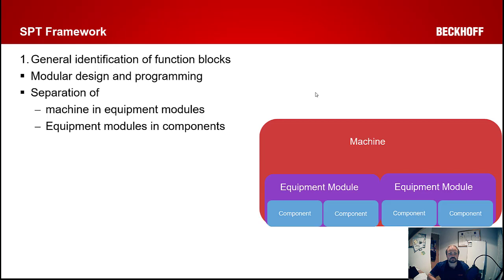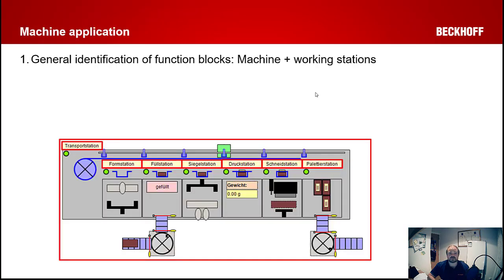So let's look at what that means for the SPT framework. The SPT framework gives you a framework for identifying your general function blocks using a modular design. We separate the machine you're going to create into essentially three component parts: a single main machine block which handles your high-level programming and state machine for the whole system, things like HMI interfaces; equipment modules that sit below that and handle the local machine sections for anything that needs to operate independently; and below that, your components — your axes, buzzers, buttons, etc.